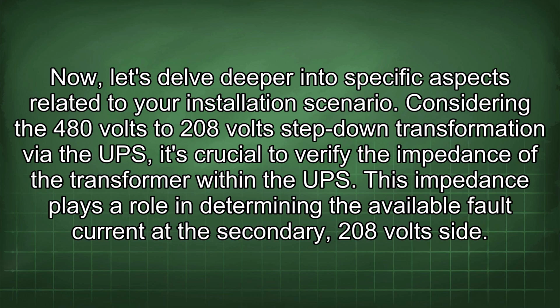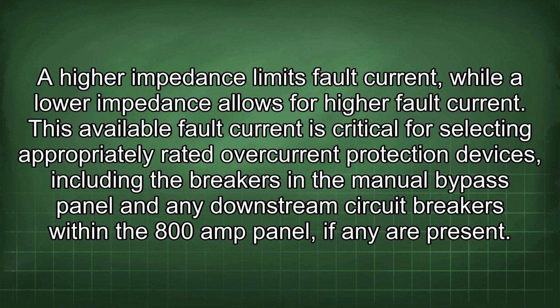Considering the 480 volts to 208 volts step-down transformation via the UPS, it's crucial to verify the impedance of the transformer within the UPS. This impedance plays a role in determining the available fault current at the secondary 208 volt side. A higher impedance limits fault current, while a lower impedance allows for higher fault current. This available fault current is critical for selecting appropriately rated overcurrent protection devices, including the breakers in the manual bypass panel and any downstream circuit breakers within the 800 amp panel, if any are present.